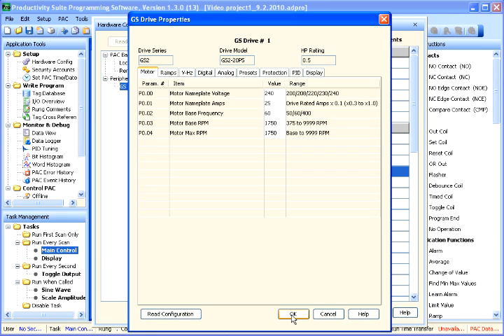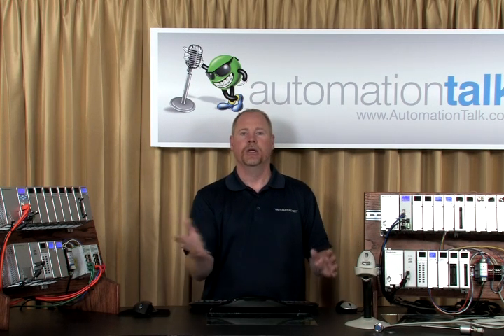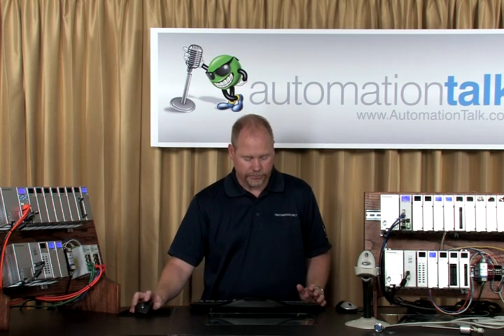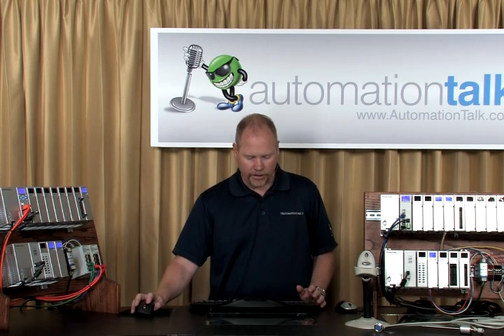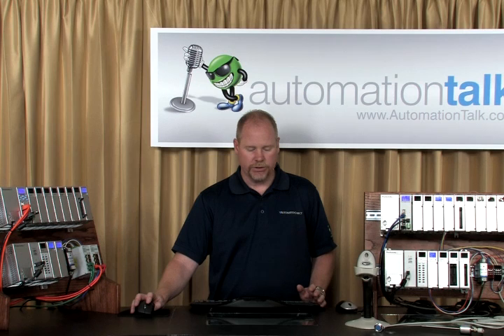This is very beneficial if you've got drives in an application, and you're having to replace a drive on the production floor. You can swap the drive out, insert another drive, and now you simply cycle power to the system, and all of your drive configuration is installed into the new drive.